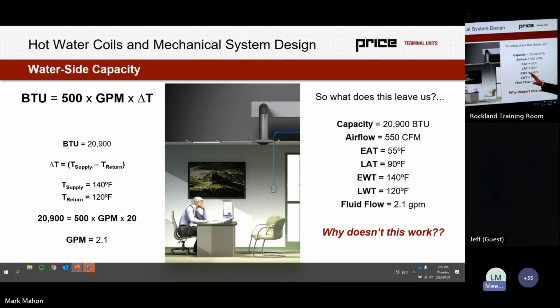I can then take that output, 21 MBH. I know my leaving air temperature, I know my entering air temperature. I need to figure out my hydronic side as well. So I take 21 MBH, and I know the supply and return water temperature I need for my condensing gas boiler. It's 140, 120. I plug that in there, I get my GPM. Bada boom, bada bing, a perfectly scheduled hot water coil.